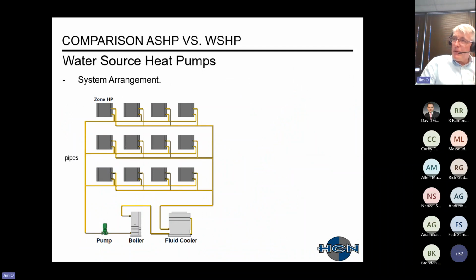Here's just a typical water source heat pump arrangement. You have multiple zones with individual heat pumps. You have a circulating pump, you have distribution piping. You have a boiler where you're adding heat. You have a fluid cooler where you're rejecting heat. Once again, just want to emphasize this doesn't have to be strictly a boiler or a cooling tower as kind of depicted here.